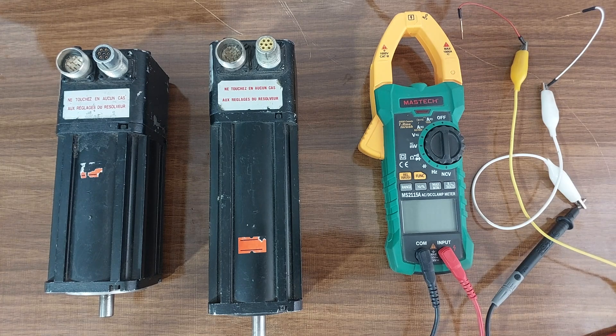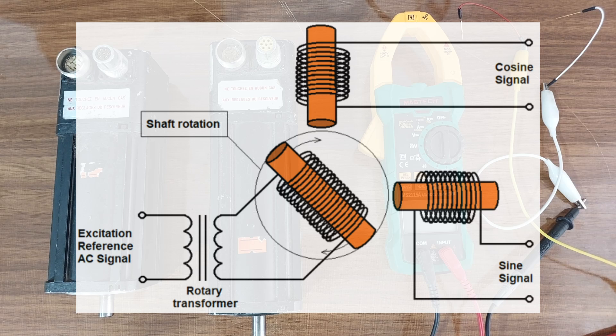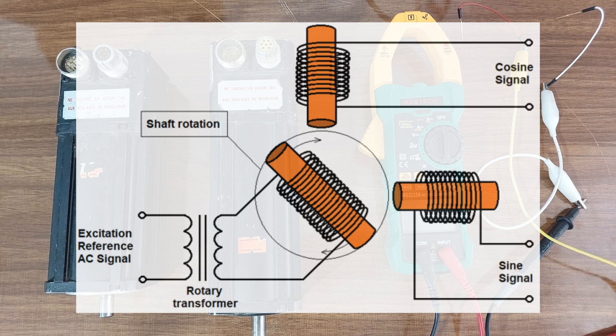So how can we test the resolver? First of all, let's review the structure of a resolver. As you can see in this figure, for a resolver we have one coil on the rotor core and two coils on the stator core — the sine coil and the cosine coil. The magnetic axis of the sine coil is perpendicular to the magnetic axis of the cosine coil, so the mutual inductance between the stator coils is zero.